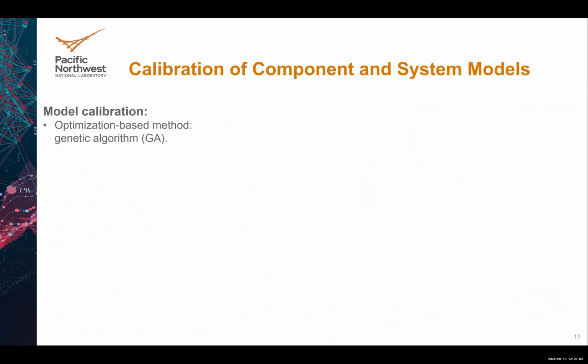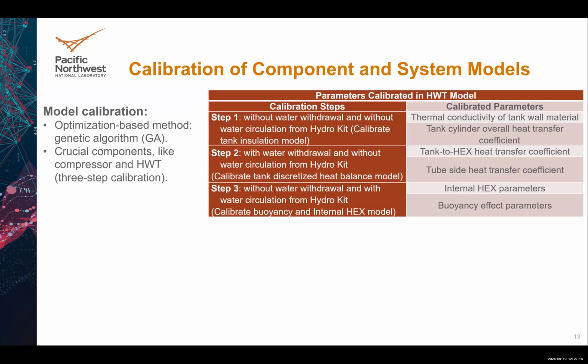We adopt a genetic algorithm to calibrate some critical components, for example, the compressor and hot water tank. For the hot water tank, we adopted a 3-step calibration. So why do we adopt a 3-step calibration? Because the hot water tank has different layers that have thermal stratification. If you want to identify the tank model correctly, you need to consider these features. So that's why we adopt the 3-step calibration.